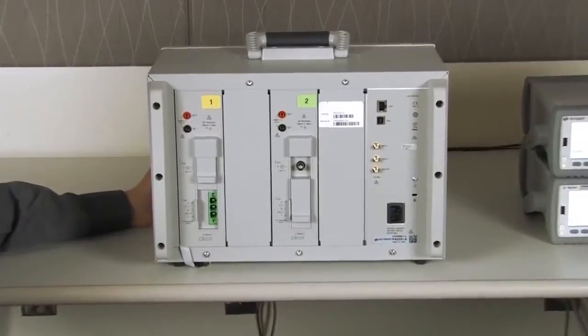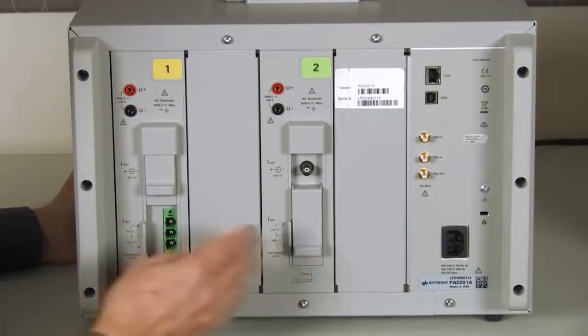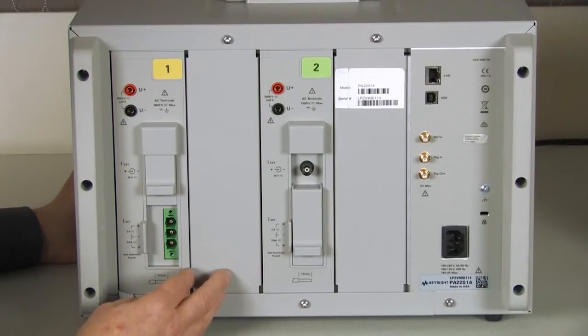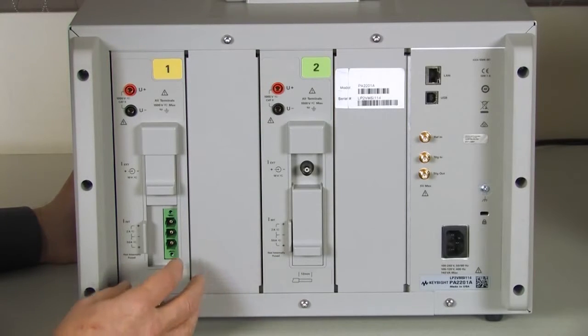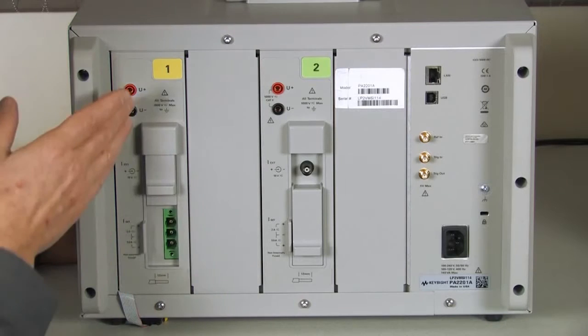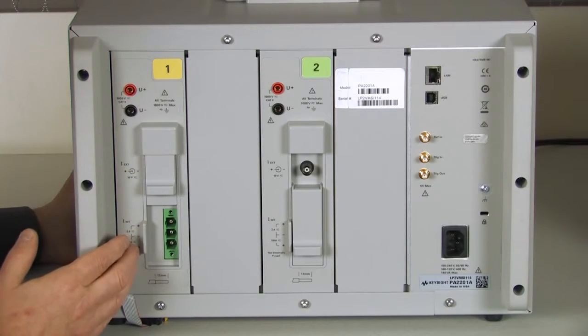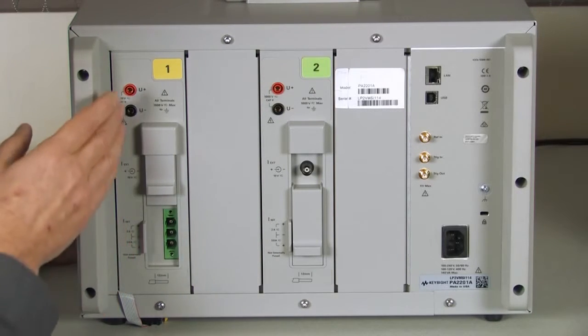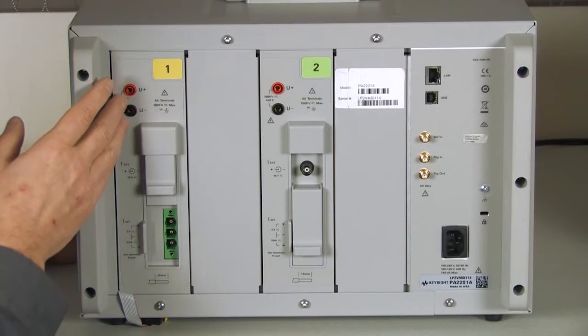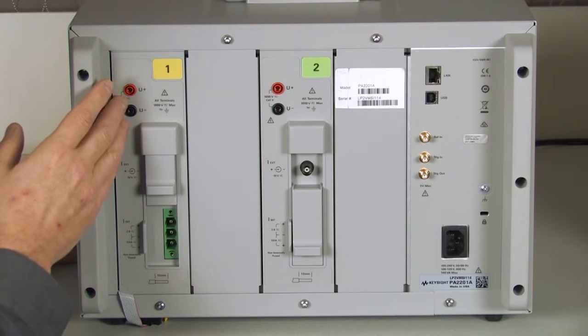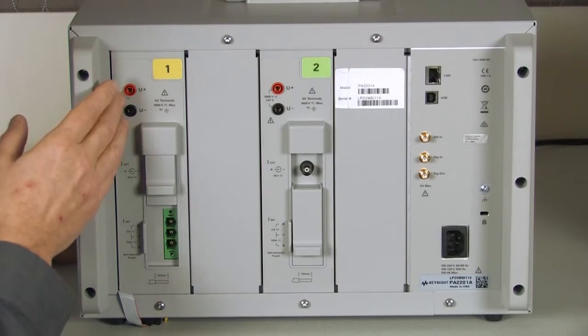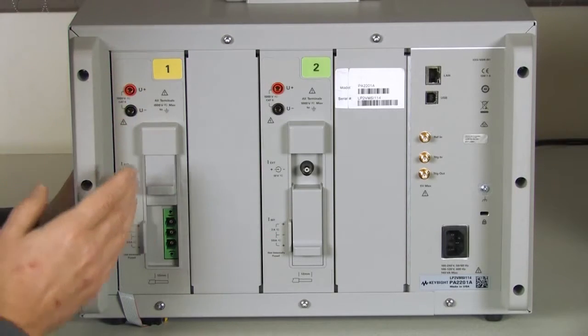First we're going to give you a tour of the connections on the back of the instrument. The first thing you'll notice are the two power channels. Unlike an oscilloscope, a power analyzer power channel has both voltage and current connections. For the voltage connections, we use banana plug connectors, rated up to 1,000 volts RMS.